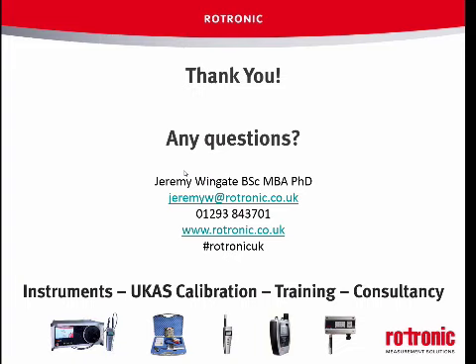Yes, thanks, Alan. No, sensors behave in very strange ways. So no, they will drift. Often you'll find that a particular manufacturer's sensor will drift in a particular way at perhaps a particular point. So we know Rotronic sensors tend to read a little bit high at the high humidities above 95%, and sort of drift that way over time.